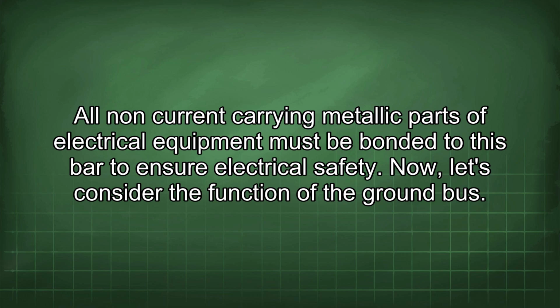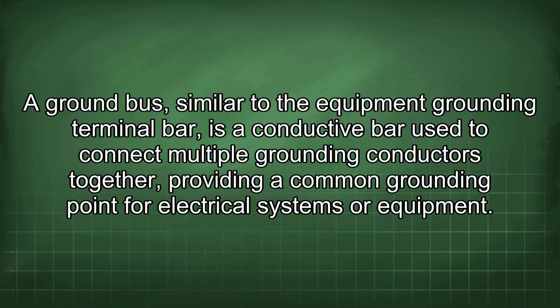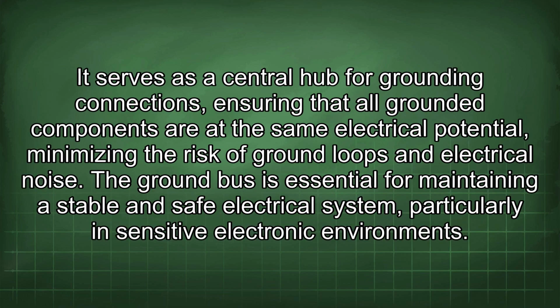Now let's consider the function of the ground bus. A ground bus, similar to the equipment grounding terminal bar, is a conductive bar used to connect multiple grounding conductors together, providing a common grounding point for electrical systems or equipment. It serves as a central hub for grounding connections, ensuring that all grounded components are at the same electrical potential, minimizing the risk of ground loops and electrical noise. The ground bus is essential for maintaining a stable and safe electrical system, particularly in sensitive electronic environments.